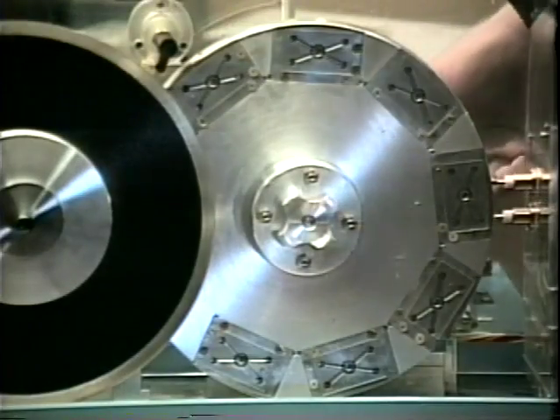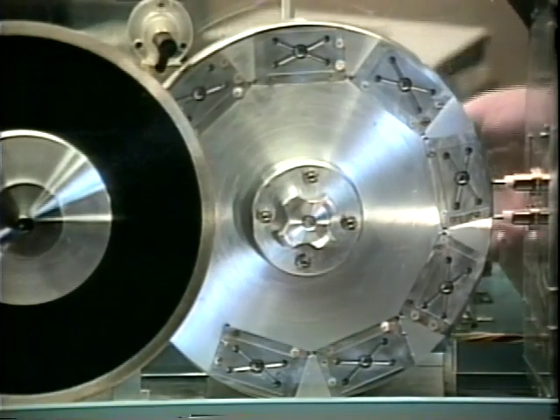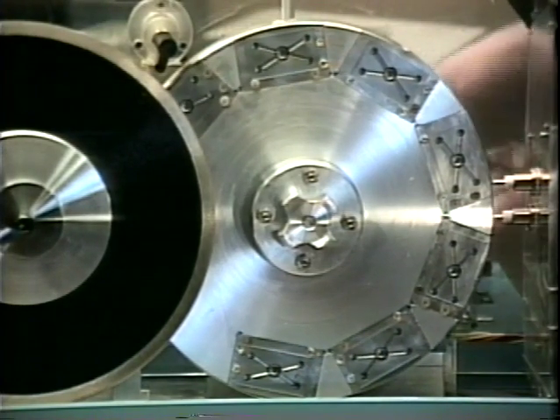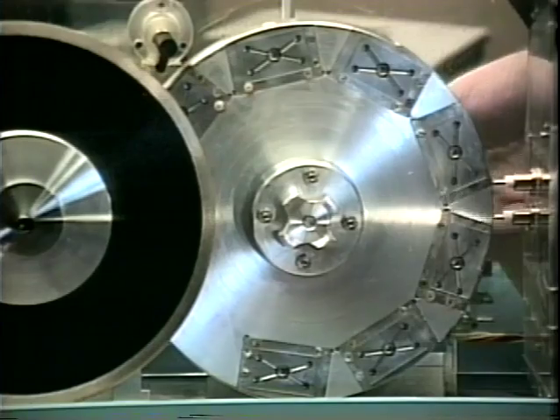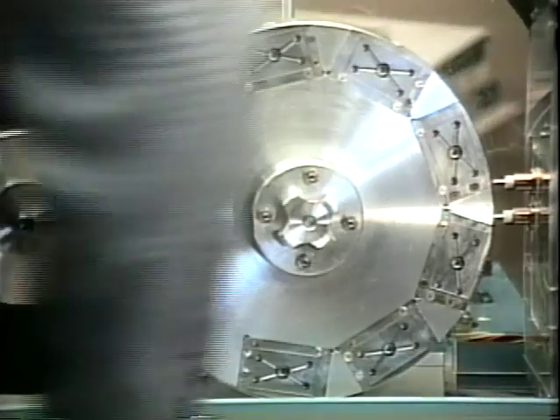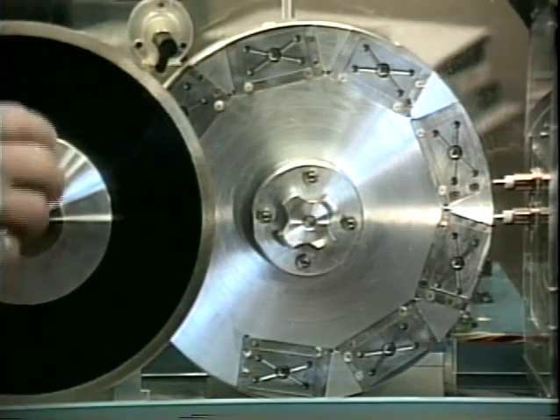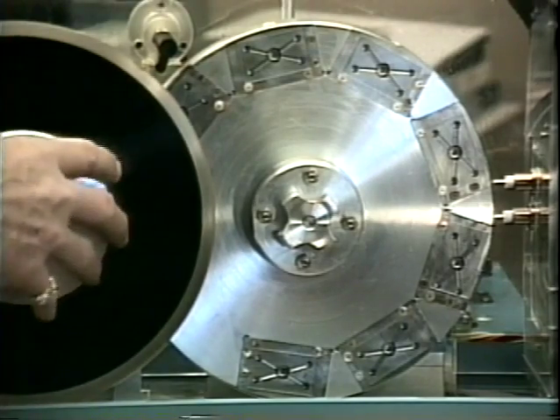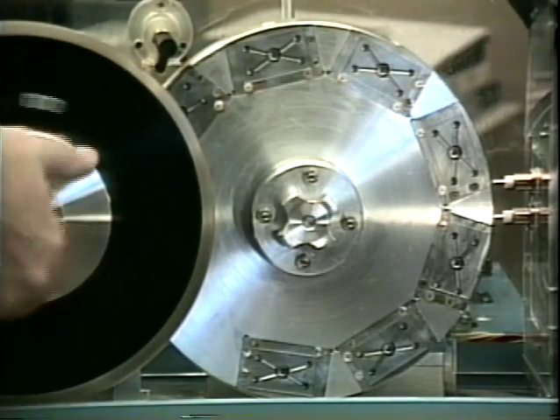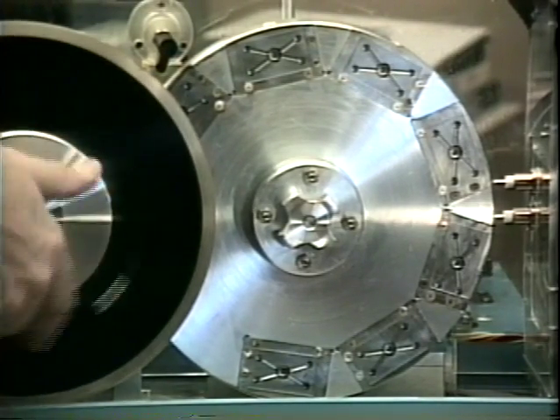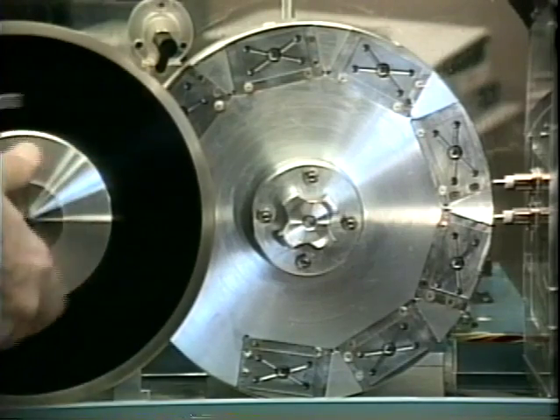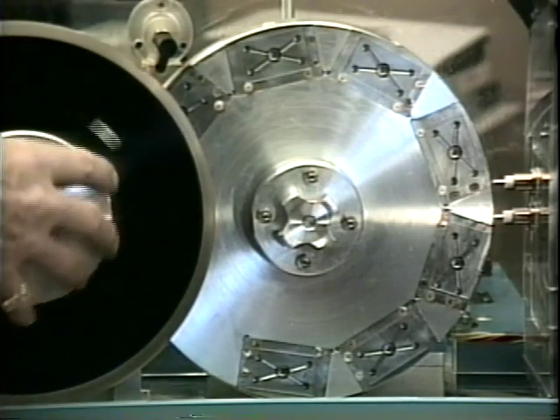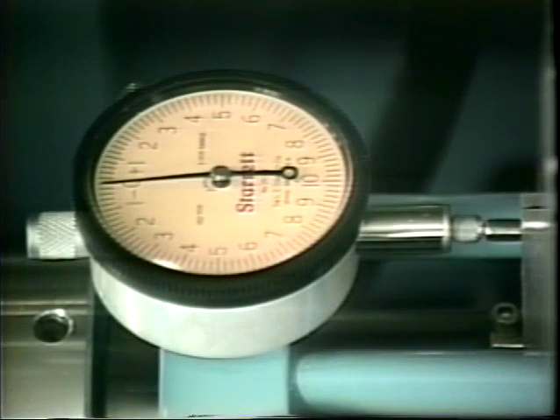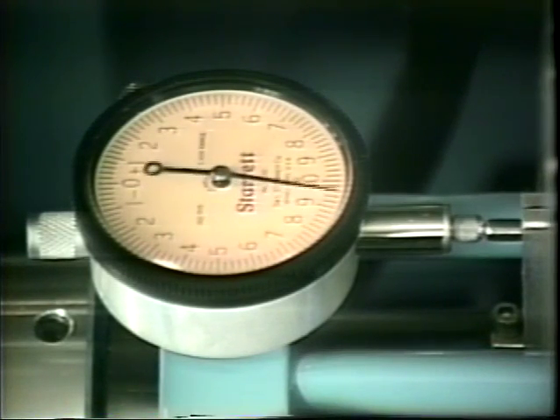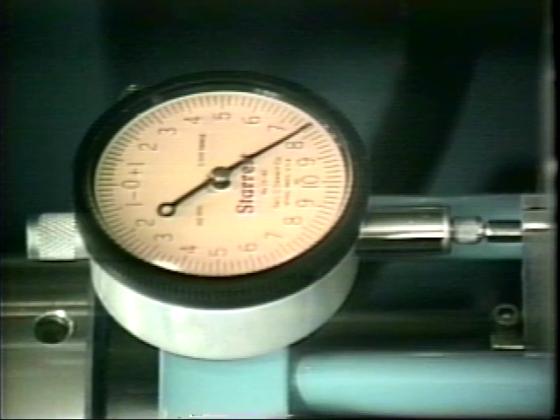We'll rotate the vacuum chuck to place this glass slide centered behind the edge of the blade. Now we'll set the blade by rotating the blade and bringing it up till it just contacts the glass slide. Then we'll back the blade off on the dial indicator 120 microns and lock the lock lever.